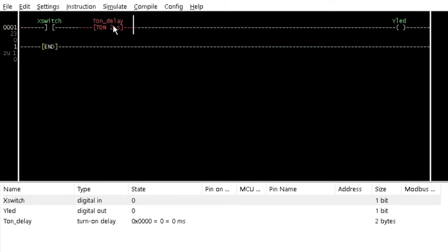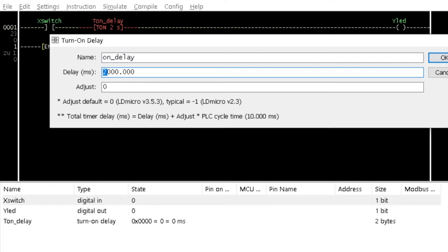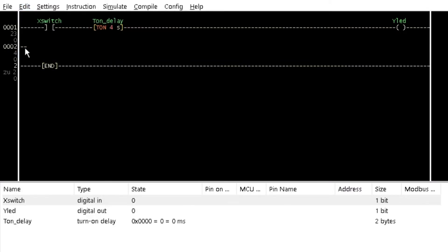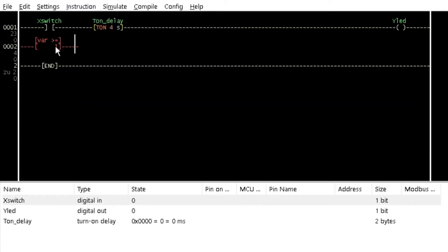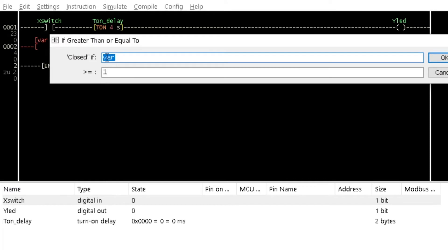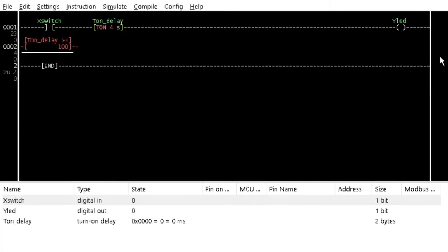Change the delay value of T on delay to 4000. Insert a rung below rung 1. From the instruction menu and compare variable option, click on insert GEQ — compare for greater than or equal. Double click on the instruction element and type the timer variable name in the 'close if' text box. Change the greater than or equal value to 100.